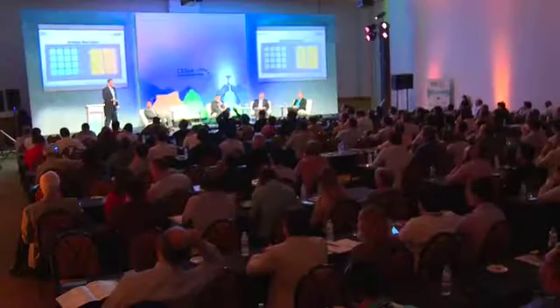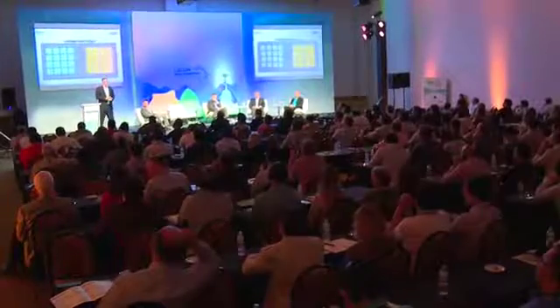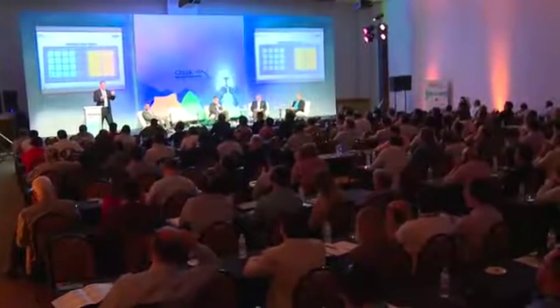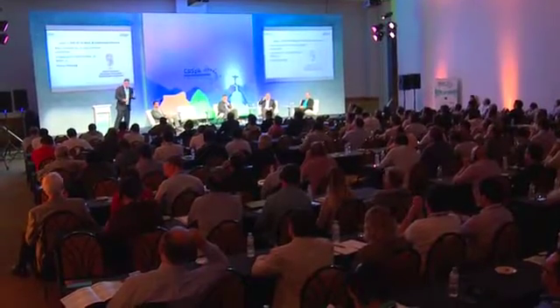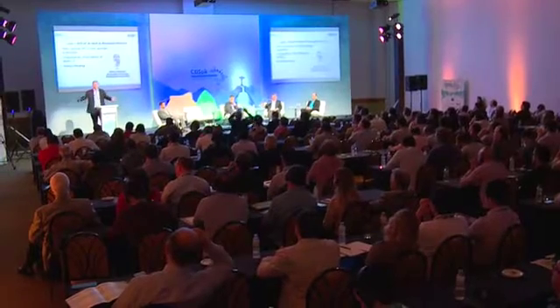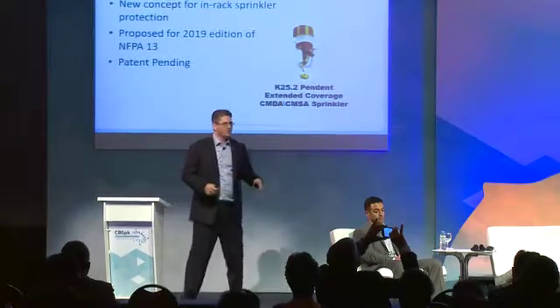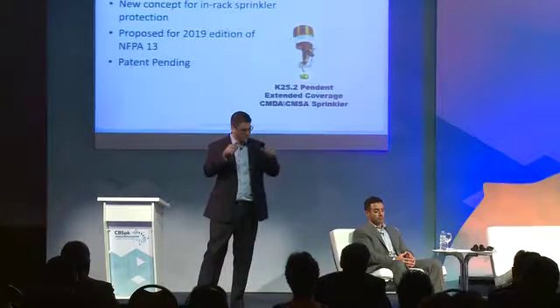So you end up with, what they've looked at and their data sheets show, something that might go 9 or 12 meters apart between in-rack levels. Pretty substantial. What we had done is look at, well, can we move the sprinklers apart more horizontally? But to do that, we're not going to use a standard coverage sprinkler. We're not going to use a sprinkler that covers 3 meters by 3 meters. We're not going to use an ESFR. It pushes down. We need extended coverage.